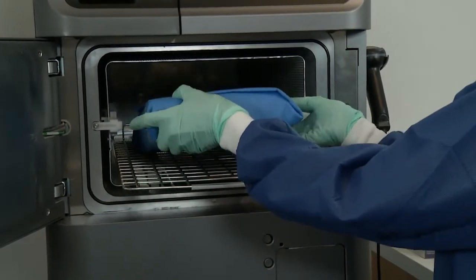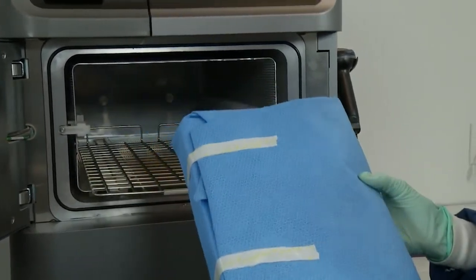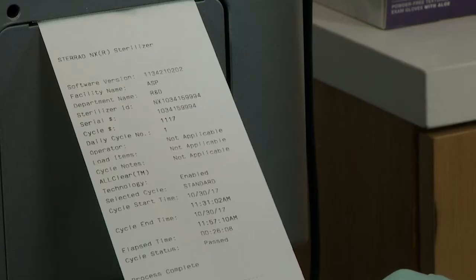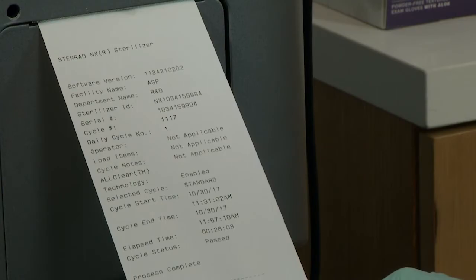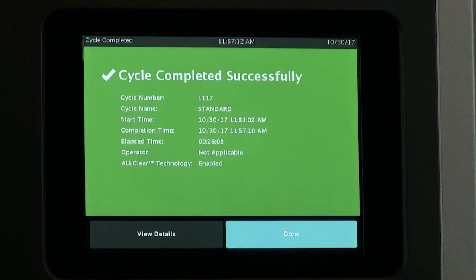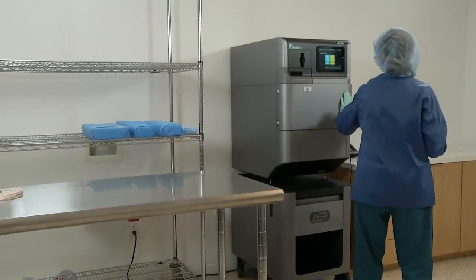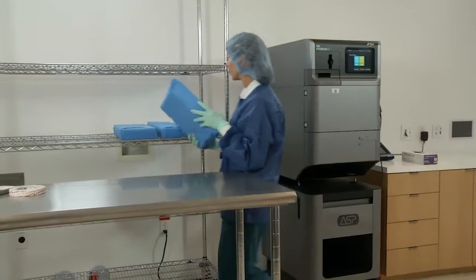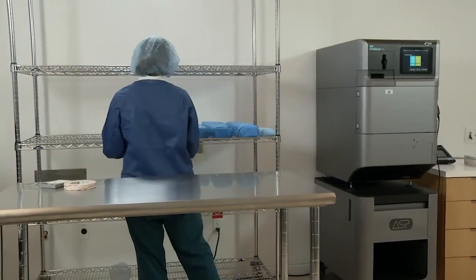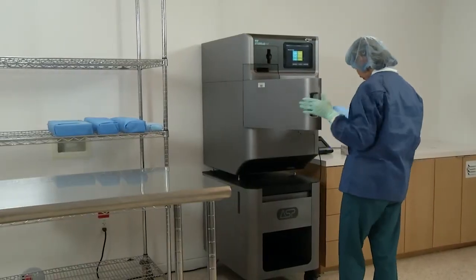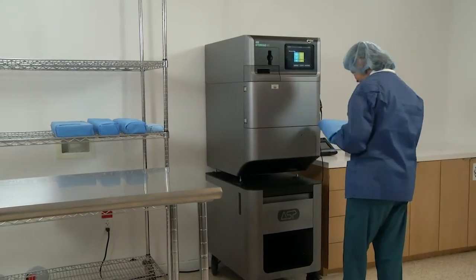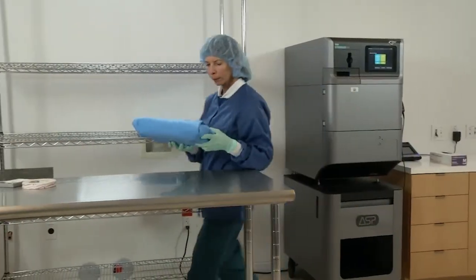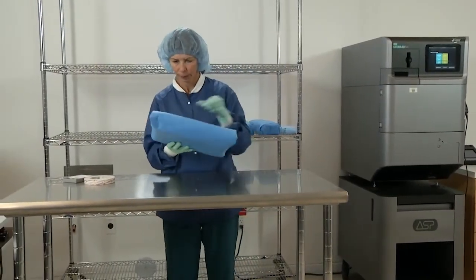Ensure that the chemical indicators on or in the sterilized packages exhibit the correct color change and that the cycle printout shows that all parameters were met. Additionally, the system screen will display the cycle status as process complete. The load is now ready for immediate use, following your hospital or healthcare facility's policy. If the chemical indicators do not exhibit the correct color change, investigate the cause and repackage the devices and reprocess.